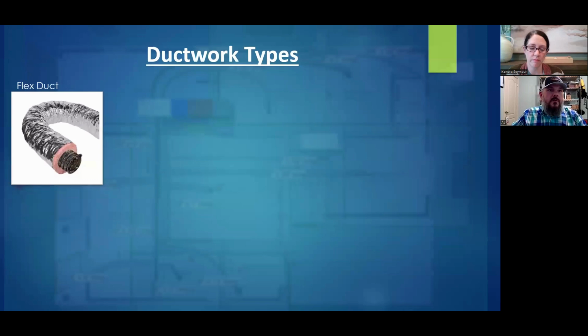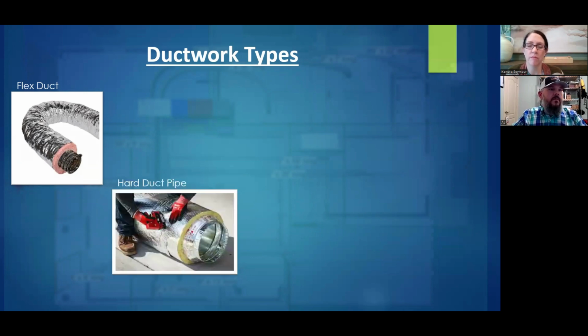So flex duct is the most common duct used. It is the easiest and least expensive to install. It has a wire helix and a very rough plastic liner. Given its roughness and flexibility, it's tough to clean effectively. I would argue that it's more effective and economical to replace it than clean it properly, should I say. Hard duct pipe. This is my preferred method. It is rigid and insulated on the outside, leaving a smooth, bare metal surface on the inside of the airstream. So the air is running through a straight, smooth piece of metal. It's not encased with a porous fiberglass material. Given the smooth metal surface, it would be the easiest and most effective for cleaning.